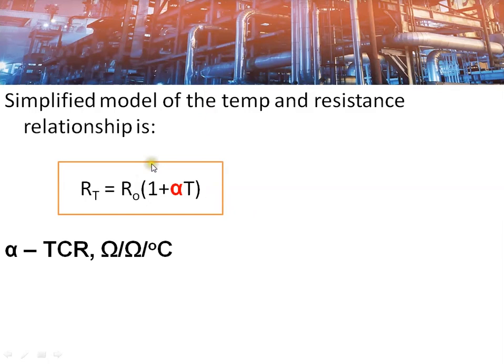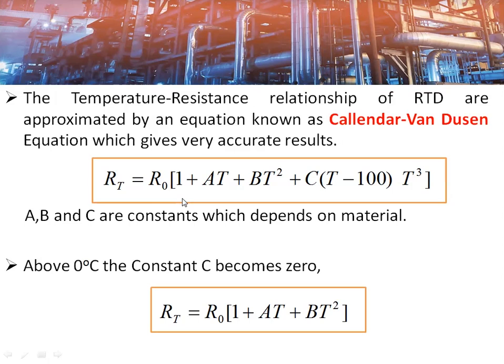This is a simplified model for the resistance and temperature relationship for RTDs, where RT is the resistance at a particular temperature, R0 is the resistance at 0°C, and alpha is the temperature coefficient of resistance. For this platinum RTD as per IEC 60751 standard, alpha is 0.00385.